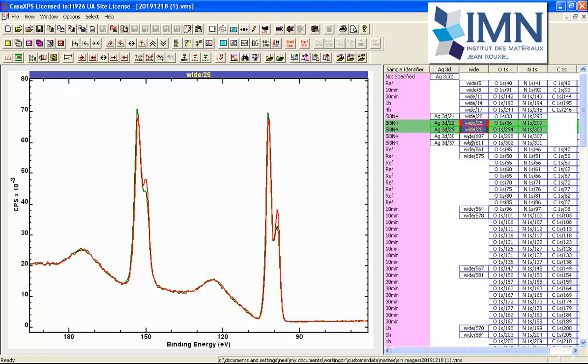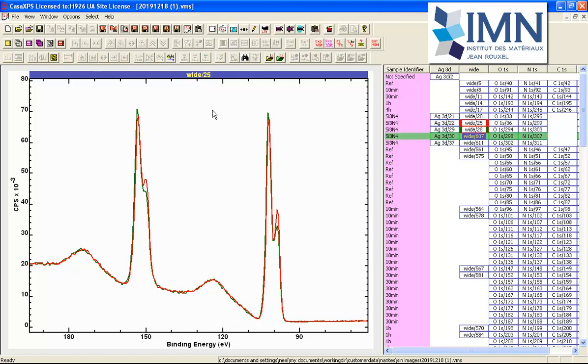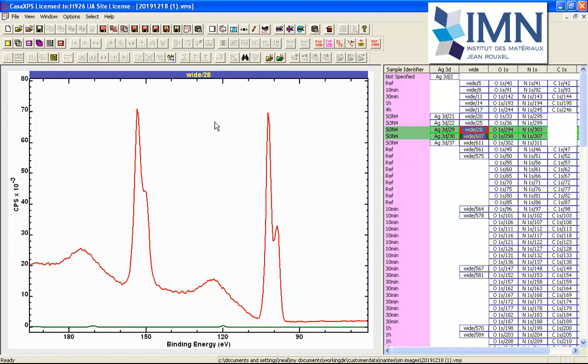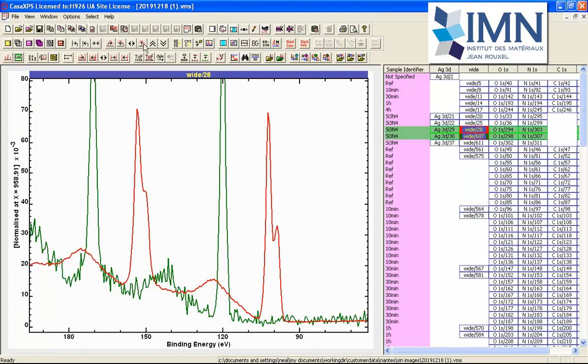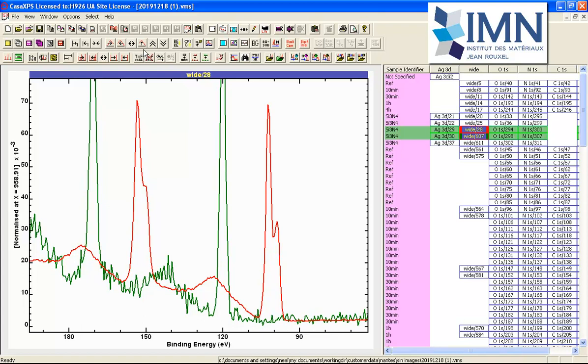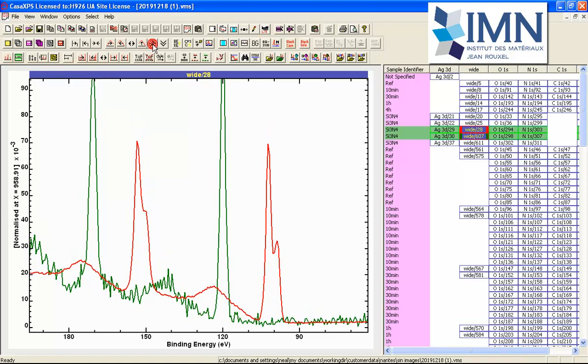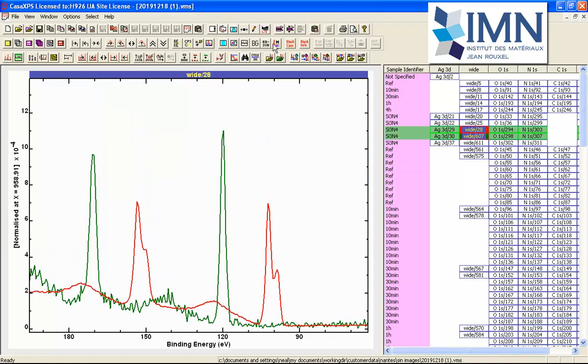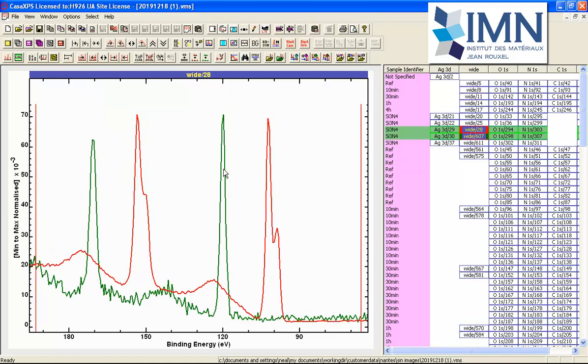The next measurement is based on using a single scan. Let's select both of these and normalize. Now I've got another measurement that represents a single scan, not a double scan. This is being measured without charge compensation. You can see the shift that occurs with and without charge compensation, and this does look more like a single peak.